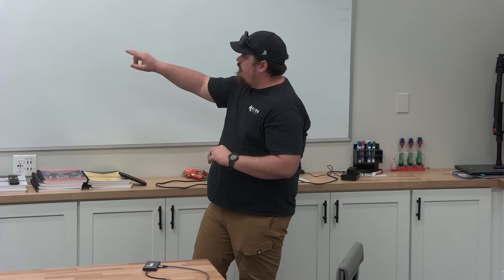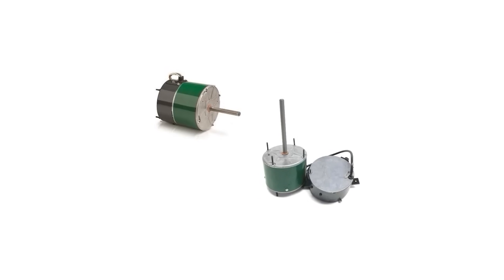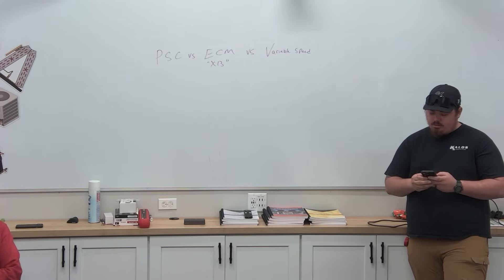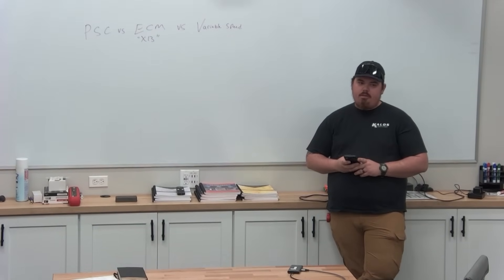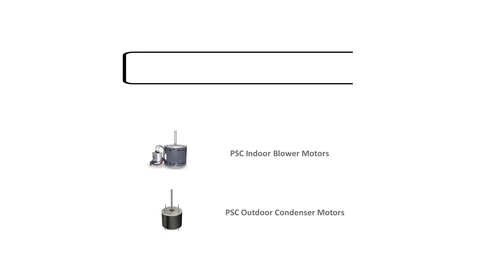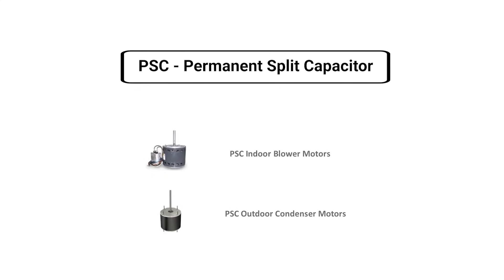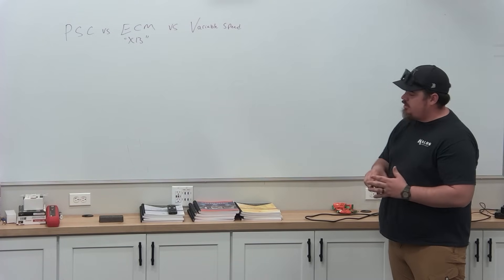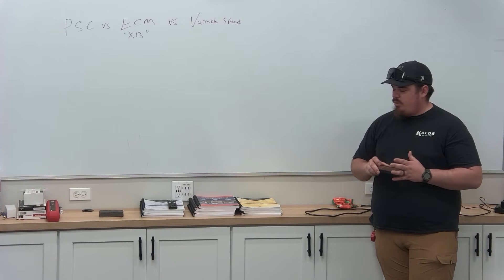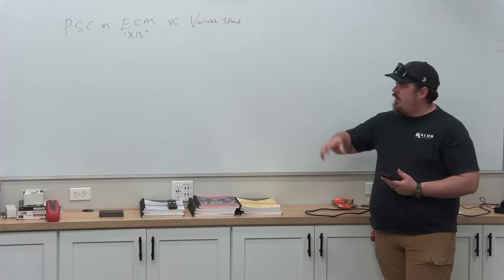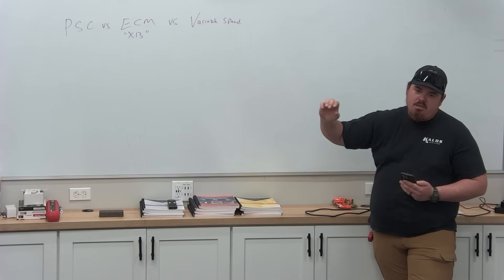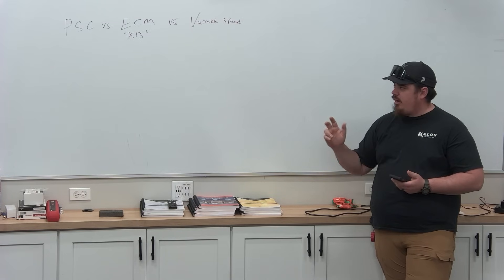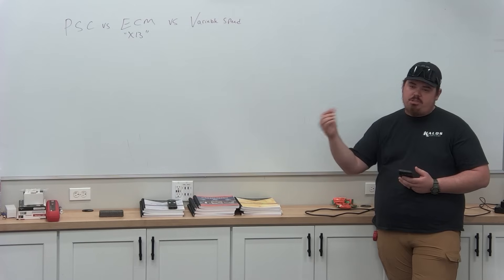PSC stands for permanent split capacitor. The systems we normally see it in are budget series and most condenser fans. It requires a capacitor for start and run functions, has a high voltage run capacitor, and your low voltage connections are tied into the motor speed tap. They're pretty simple — low, medium, or high. High is traditionally always used on heat, but you always want to ensure when installing that you're checking what those speed taps are.